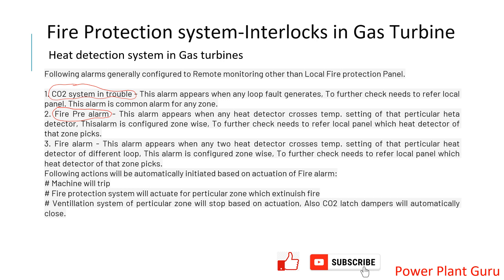The second alarm is 'fire pre-alarm,' which is a warning that fire conditions may be developing. For example, if there are two sensors in a zone — one set at 316°C and another at 300°C — and one sensor is crossing its limit but the other is not, you will get only a pre-alarm. This tells you that one sensor has triggered and the other may follow soon, so you can prepare, reduce load, or investigate why this is happening.